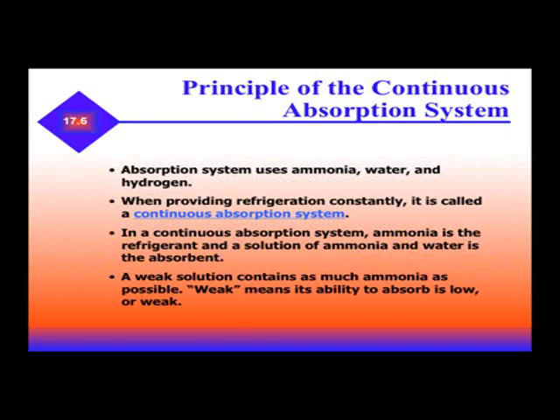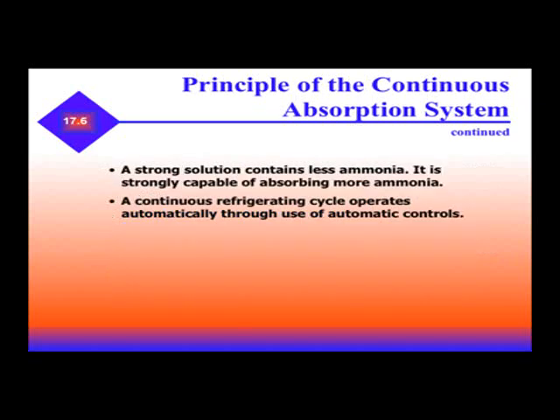Absorption systems use ammonia, water, and hydrogen. When providing refrigeration constantly, it's called a continuous absorption system. In a continuous absorption system, ammonia is the refrigerant, and a solution of ammonia and water is the absorbent. A weak solution contains as much ammonia as possible — weak meaning its ability to absorb is low or weak. A strong solution contains less ammonia and is strongly capable of absorbing more ammonia.